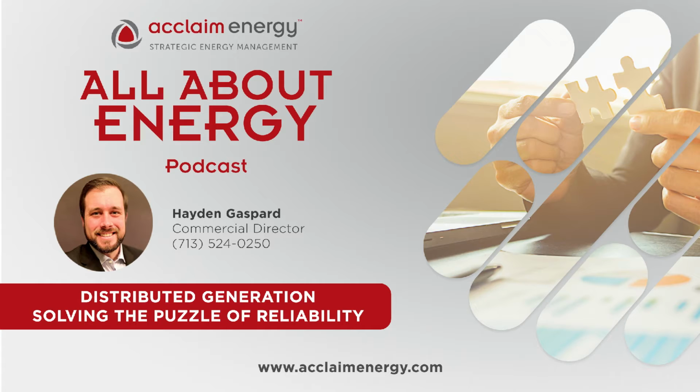It's an exciting technology, and while it's not necessarily new, it is still a bit of an unknown to a lot of businesses and government entities and medical facilities that could make it a useful piece of their energy portfolio. So what is distributed generation? In short, it's just a way to utilize your emergency generator's ability to put electricity back onto the grid. You do that through what's called a paralleling switchgear, which we'll touch on later, but simply it's just a switchgear that allows you to either supply your facility with power that the generator produces or to send it back to the utility grid, or to do both at the same time.